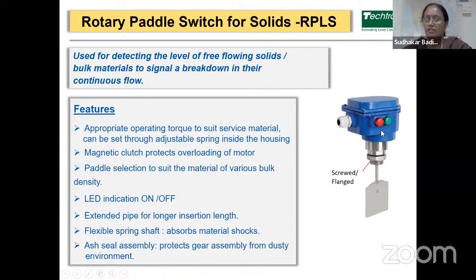Then LED indications are available as on and off. That is, when the paddle rotates, it gives you the green indication, and when the paddle stops, when the solid level touches this paddle, it shows you the red color. The extended pipe is for a longer insertion length. That is, this is the extension pipe, and that can be extended to 1500 mm as per your requirement. Then a flexible spring shaft is also provided to absorb the material shocks. Then an ash seal assembly is also provided to protect the gear assembly from dusty environments. These are the optional features of this switch.